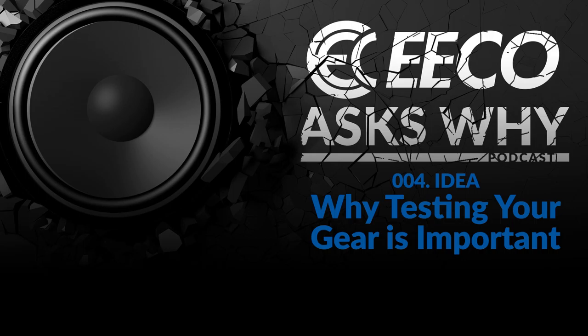an electrical product. That was great, Dan. You really walked through all the different tests there, the injection testing. I'm glad you were able to get to that. I know that gets brought up a lot. So let's take it to the technicians that we're trying to support here on EECO Asks Why. Say a breaker's tripping, and you've been called out to evaluate that situation. You're the guy. What steps and tests would you take to begin diagnosing the system?